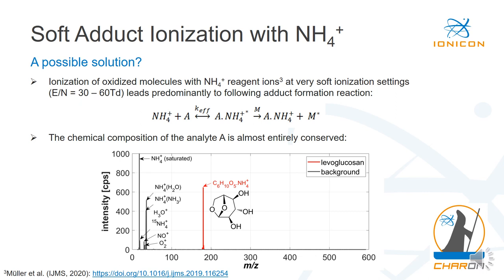When we ionize our molecules with ammonia at very soft ionization settings of only 30 to 60 Td, this leads predominantly to ammonium adduct formation. With this adduct formation, almost the entire chemical composition of the analyte is conserved. As an example, the mass spectrum of levoglucosan in ammonium mode shows only one single peak — namely C6H10O5 clustered with ammonia. There are no fragments and no dimers or other clusters visible.